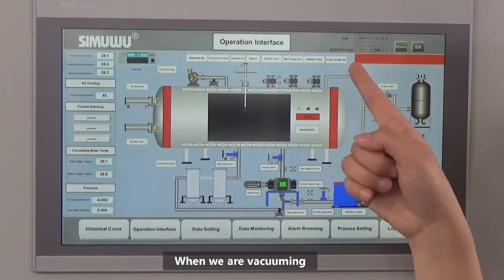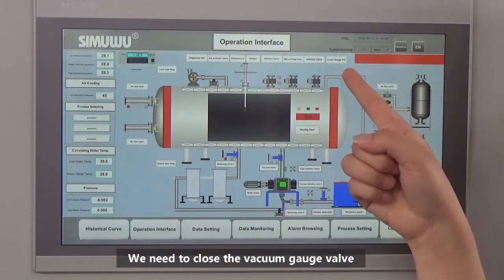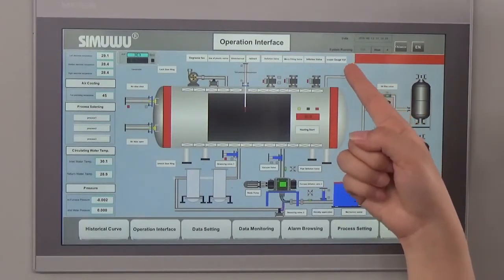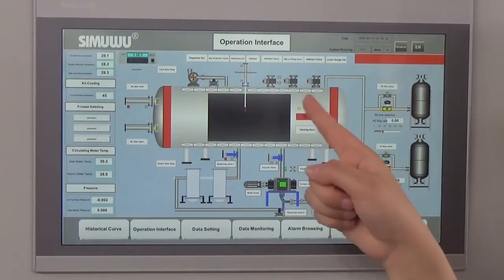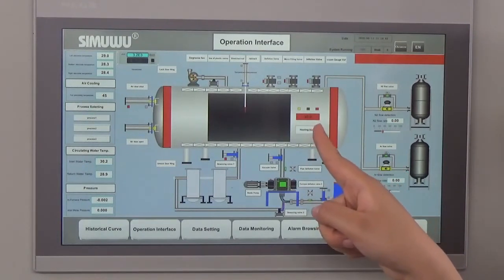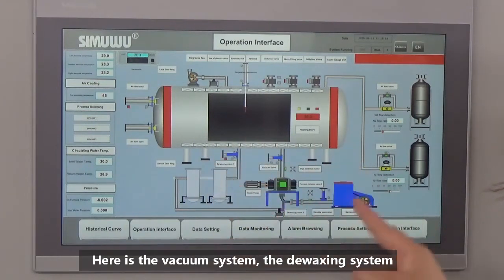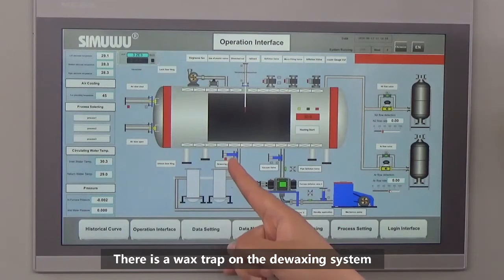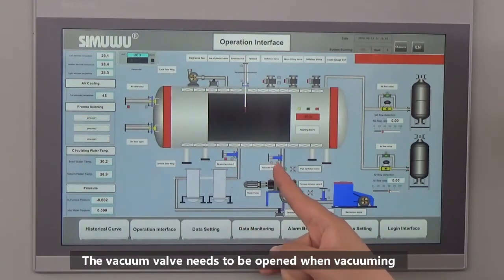When we are vacuuming, we need to open the vacuum gauge valve. When we are not vacuuming but de-waxing, we need to close the vacuum gauge valve. Here is the temperature display inside the furnace. This button is for heating — after setting the process, click here to start heating. Here is the vacuum system and the de-waxing system. There is a wax trap on the de-waxing system which needs to be opened to let the wax flow into the de-waxing tank. The vacuum valve needs to be opened when vacuuming.